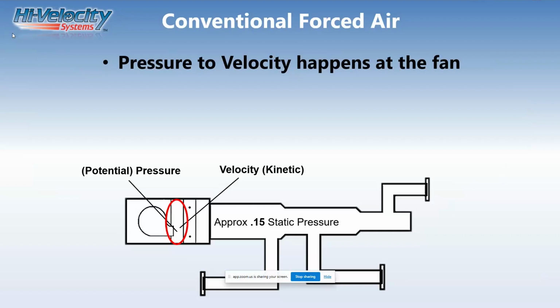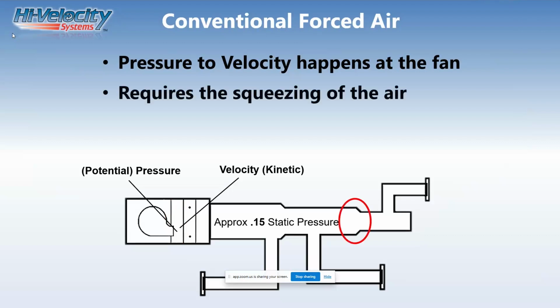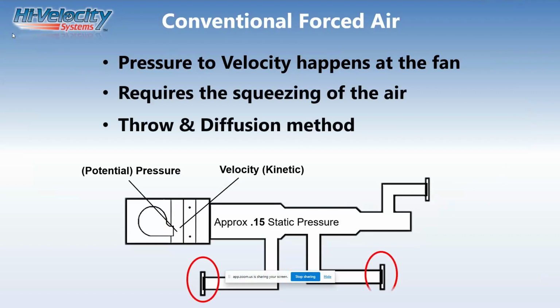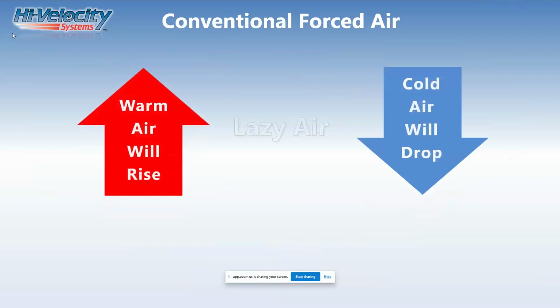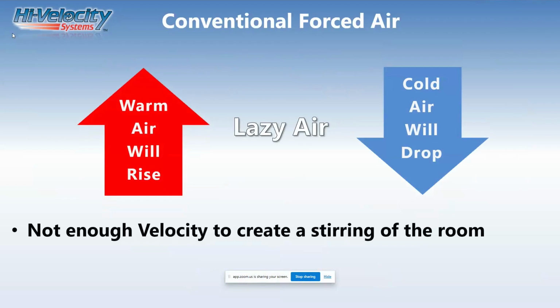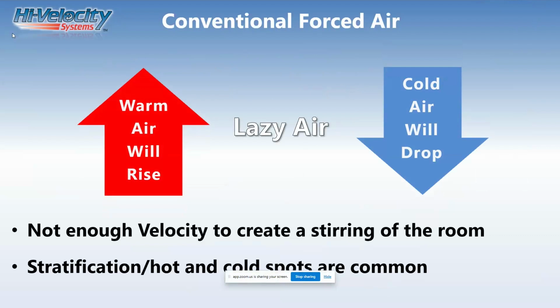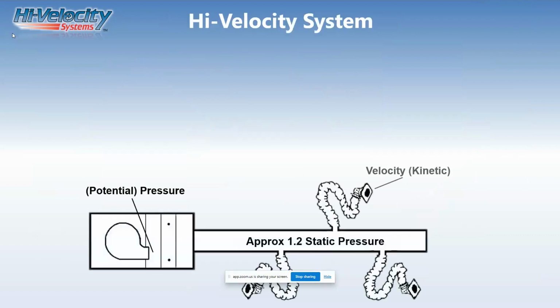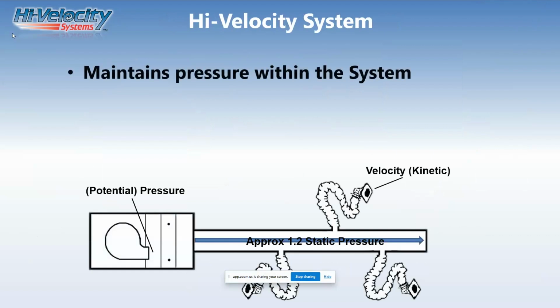So conventional, let's talk about that. Pressure is converted to velocity at the fan cabinet. It requires squeezing of the air. The throw and diffusion method is very common. And what we're getting out of conventional forced air is the warm air will rise, the cold air will drop, lazy airflow, not enough velocity to create any stirring of the room, and stratification of hot and cold spots are very common.